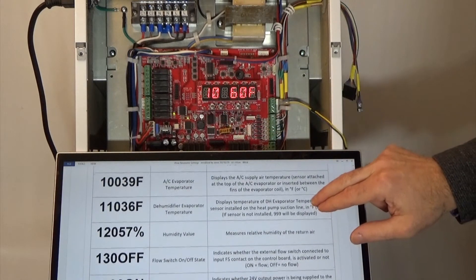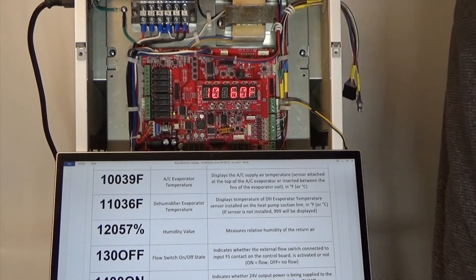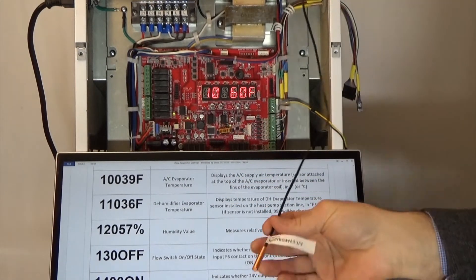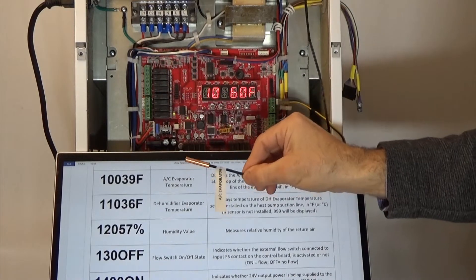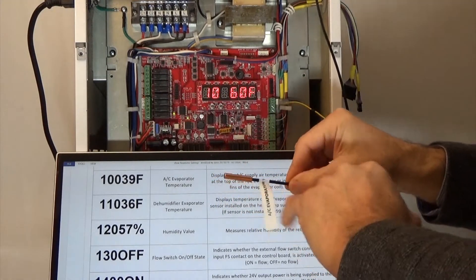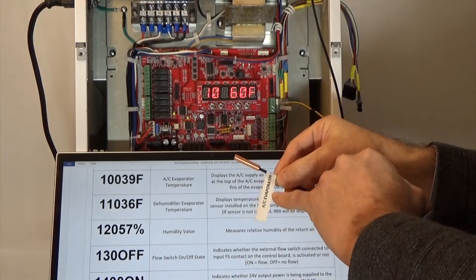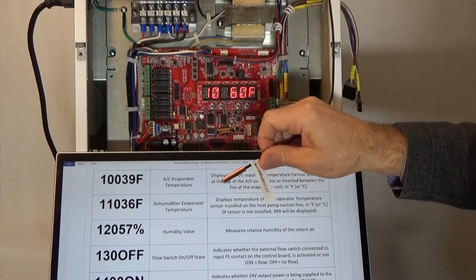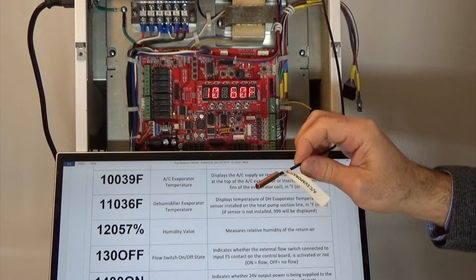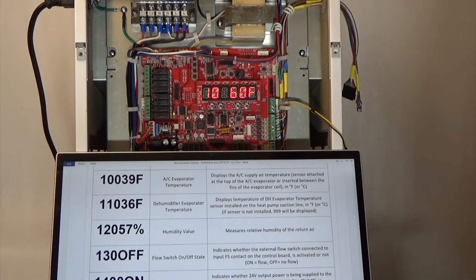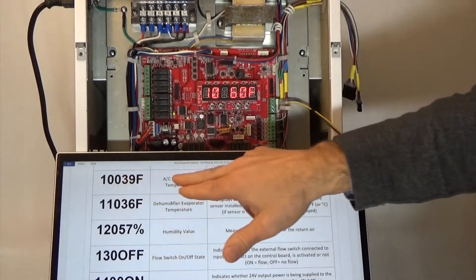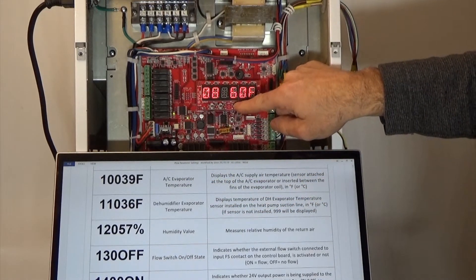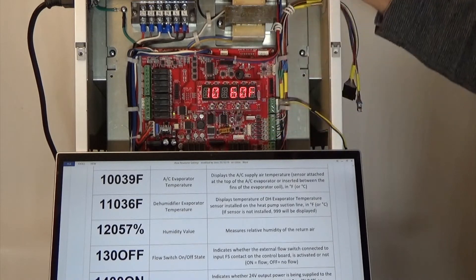Parameter number ten is the AC evaporator temperature sensor. When you open the box of the unit, laying on top of the coil you have this sensor — it could be copper or stainless steel, but it'll be marked AC evaporator temperature sensor. This installs in the top of your AC coil and measures the temperature coming off the top of the coil, for freeze protection. Parameter number ten gives you that value. It's seeing the same temperature as the other sensors because the unit is off.